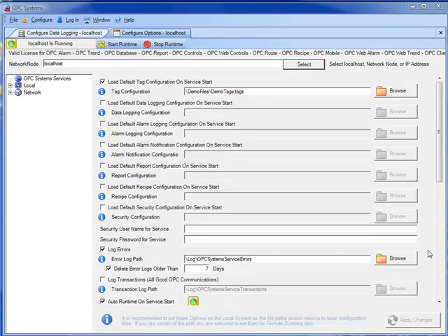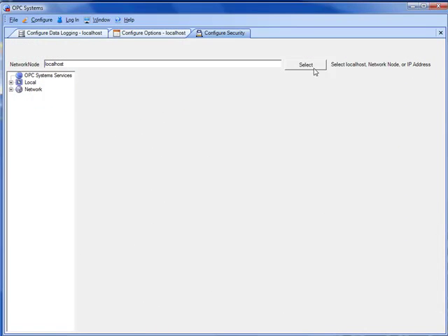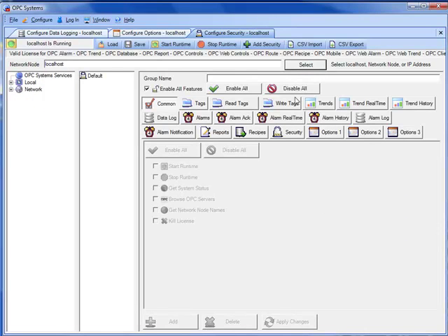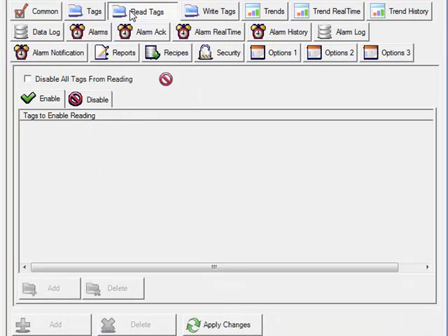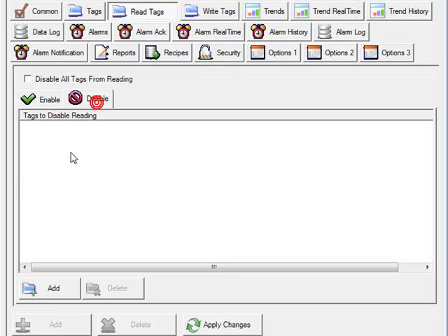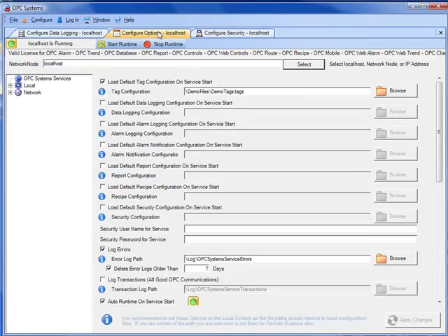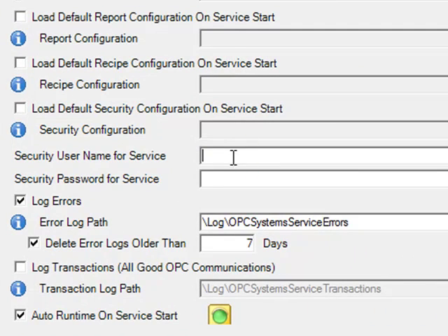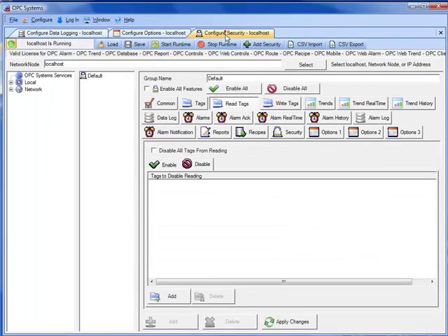If you are logging data from a remote service that has security enabled, to restrict reading tags, you will want to specify a username and password that has privileges appropriate to read the tags you are interested in logging. Under configure security, there is the read tags tab. And if you have disabled all tags from reading, or even specific tags, or even specific tags to be read from client applications, then under the data logging service that is connected to that remote service, you want to go to configure options on the data logging service and specify the security username and security password. So the data logging service will have access privilege to the data that it needs to log. Otherwise the data will not be available, and you will not be able to log the data.